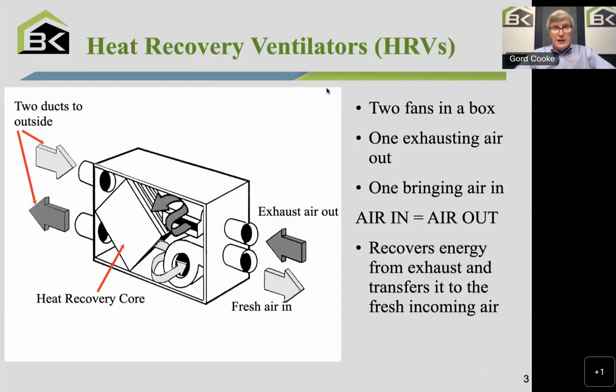And people often ask me, so how much do they cost to run? Now, depending on where you're located, your community, depending on how electricity is generated and the cost of electricity in various communities, typically the cost to run those two fans, if I left it running 24 hours a day, 365 days of the year, is in the order of about $30 for new HRVs because they have better fans in them. Old HRVs, it might have been as much as $80 to $100 for the electrical cost to run the fans. So the newer devices, much more efficient, better motor technology, about $30 a year.